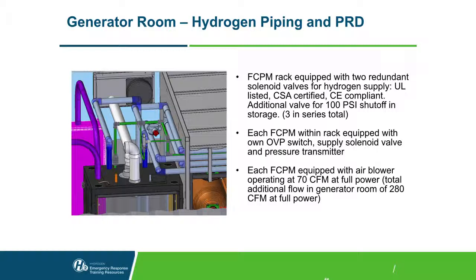So we have the fuel cell power module rack equipped with 2 redundant solenoid valves for the supply. Each rack has an overpressure switch, supply solenoid valve, and pressure transmitter. So again, constantly monitoring pressure and temperature, and if it sees a problem, a sudden drop in pressure or a hydrogen sensor goes off, it will take the appropriate action.